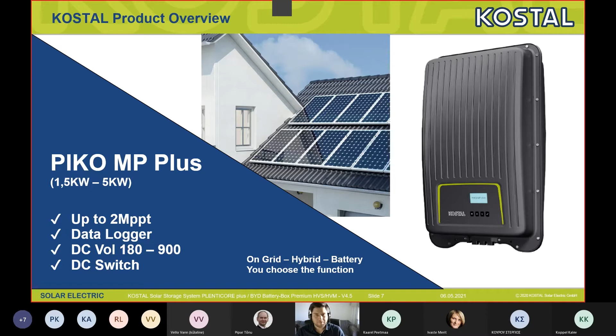It's a fully flexible inverter, because you can use it either as a normal on-grid inverter, or as a hybrid inverter combining PV modules and batteries, or as a battery inverter, meaning on the DC side of the inverter you can connect only batteries. So you choose the function of this inverter.